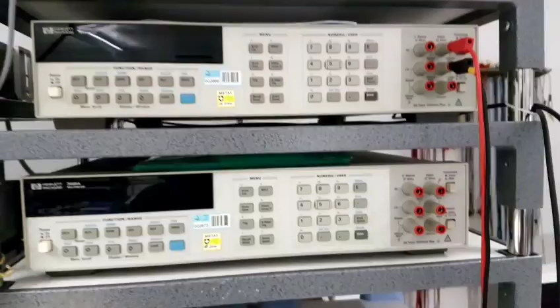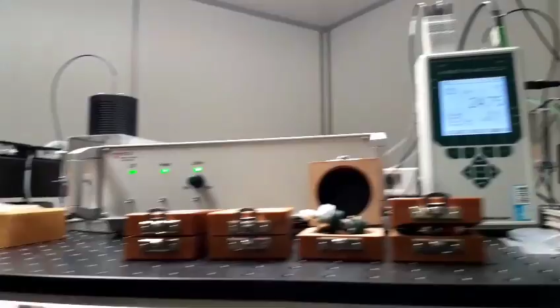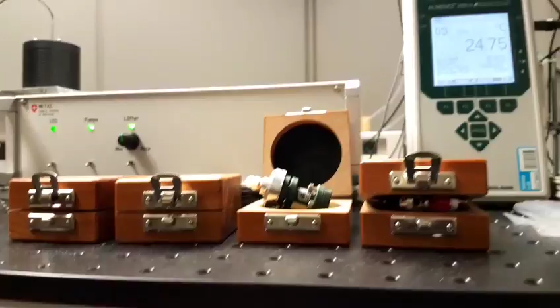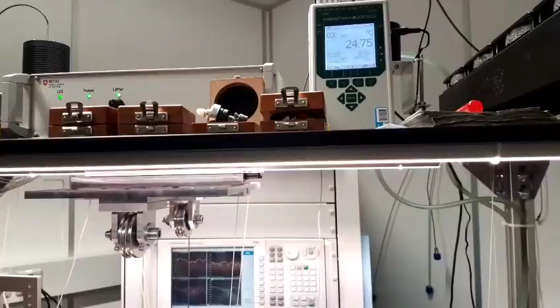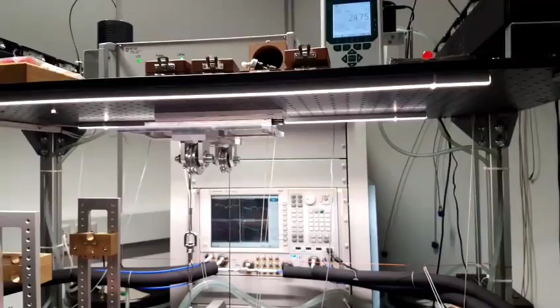The power measurements are not so sensitive, and we can compare each connector. So we don't need to send it every year. Maybe we send it every 2 years or even less, because we can compare the different standards against each other. If they don't change, then you don't need to recalibrate. If you have more standards than you need, you can monitor the stability of the standards, assuming that not all are drifting in the same direction. But that's a bit unlikely. So from time to time, we send them.